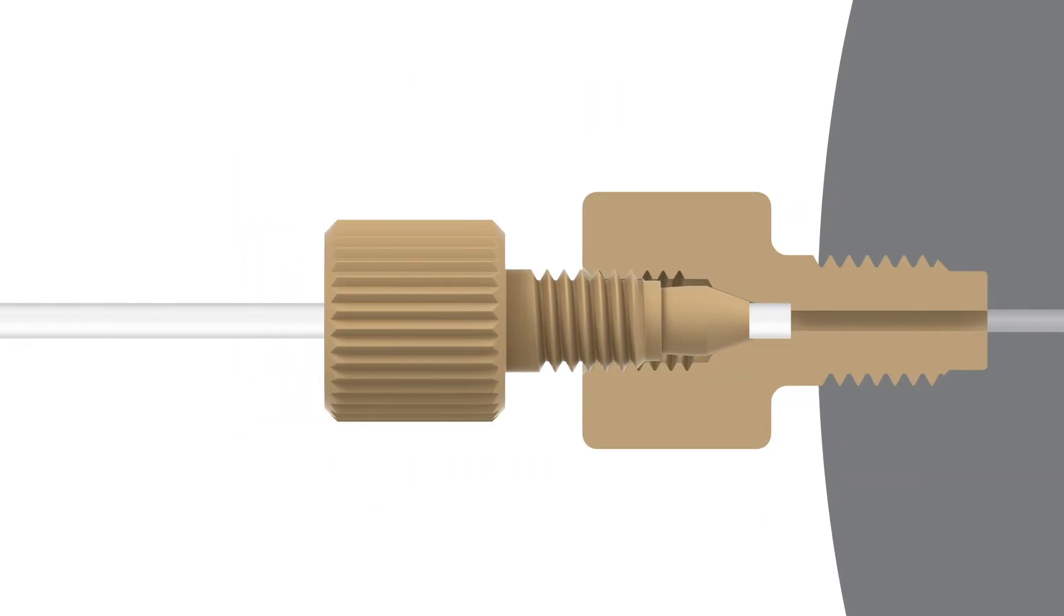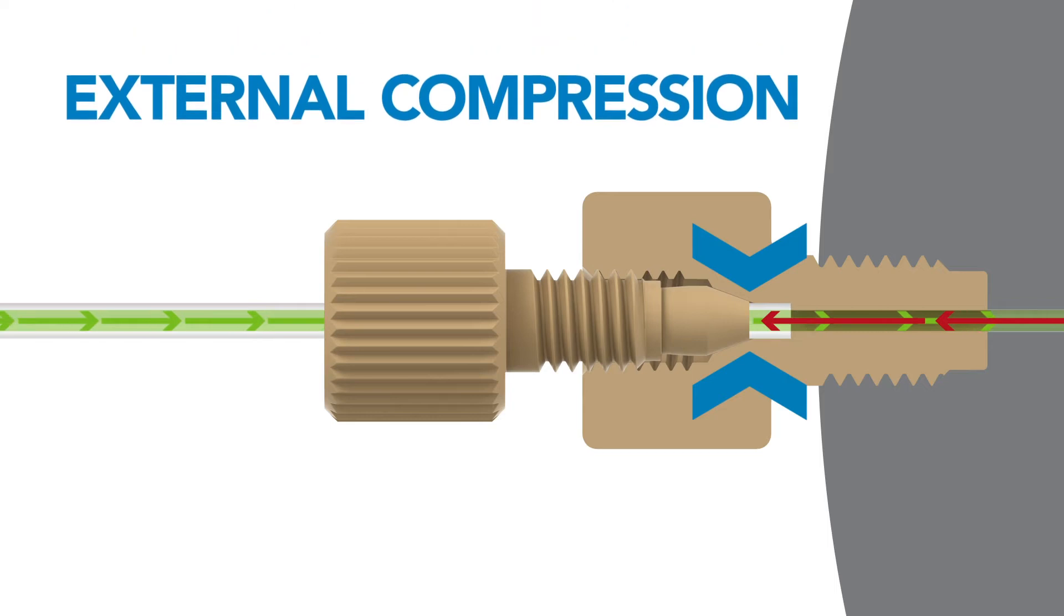Fittings have two primary functions. They prevent liquid or gas from leaking out of the flow path, and they hold the tubing in place against the opposing pressure in the flow path through a process called external compression.